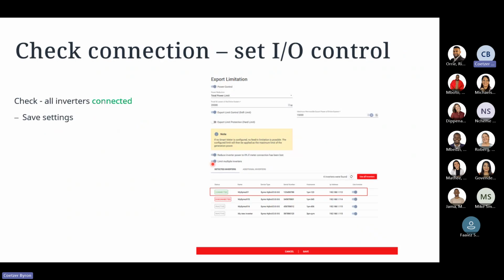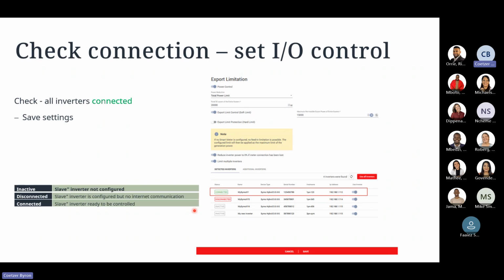From here, the unit will try to detect the inverters that it can find in the TCP network. It will find the additional network devices and notify you of what IP address it has found. This allows you to control and see which units are communicating correctly. If it shows inactive, it means the slave inverter is not configured correctly. Disconnected means the inverter is configured, but there is no network communication, so it could be a simple IP address conflict with the units. Connected means the slave inverter is ready to be controlled fully via the master unit.